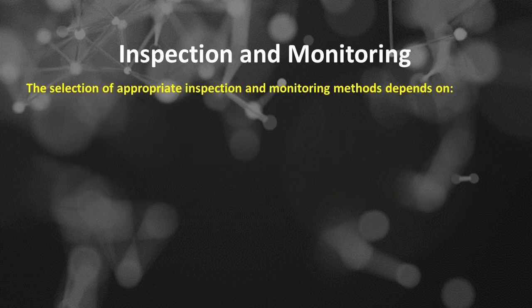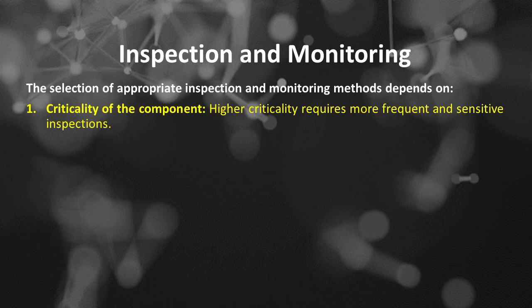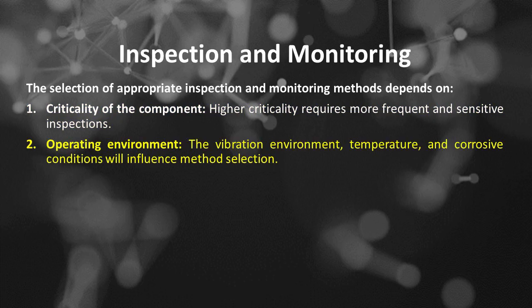The selection of appropriate inspection and monitoring methods depends on: Number 1, criticality of the component. Higher criticality requires more frequent and sensitive inspections. Number 2, operating environment. The vibration environment, temperature, and corrosive conditions will influence method selection.